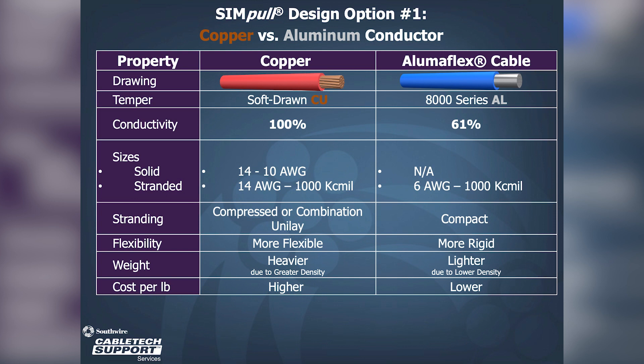For aluminum conductors, we offer our 8000 series aluminum alloy trademarked as Alumaflex. Alumaflex conductors are 61% as conductive as copper and are offered in solid conductors from 12 gauge to 4-aught, and in stranded conductor sizes from 12 gauge to 2,000 kcmil. Our standard stranded configuration is compact aluminum, which is more rigid than our stranded copper designs.